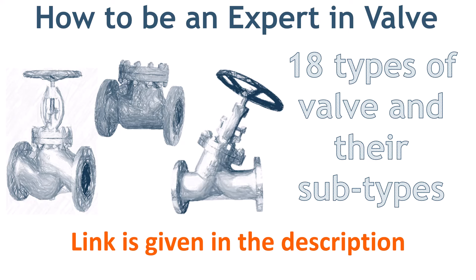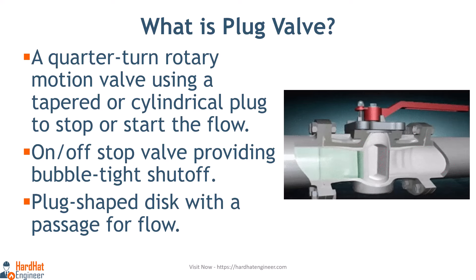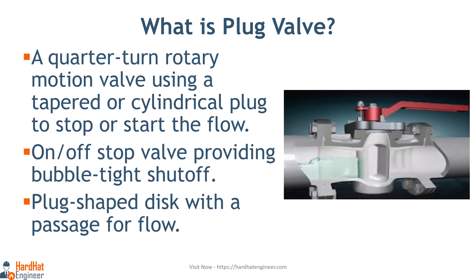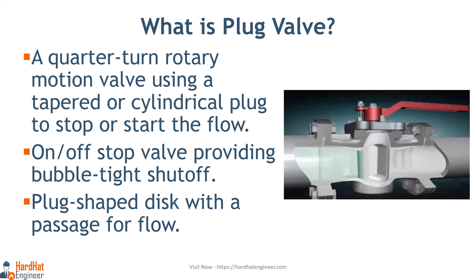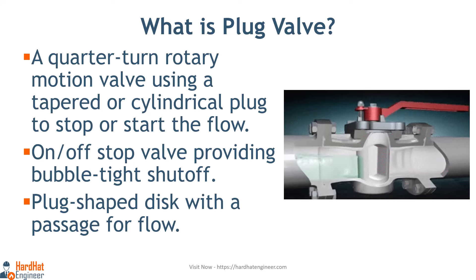Next, what is a plug valve? A plug valve is a quarter-turn rotary motion valve that uses a tapered or cylindrical plug to stop or start the flow. The disc is plug-shaped and has a passage to pass the flow. This bore passage is in line with the flow in the open position. When the plug is turned 90 degrees from the open position, the solid part of the plug blocks the flow.